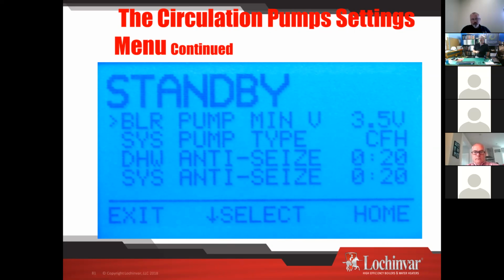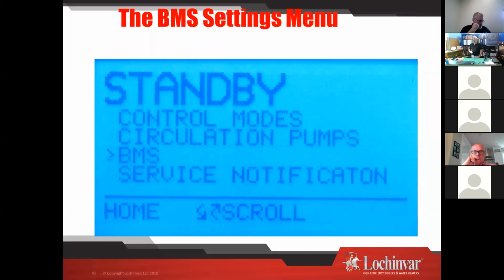Boiler pump minimum voltage is going to be set for 3.5 volts, and that's the minimum rate that it's going to run that pump. Now on the display screen, it shows you your boiler pump rate output, it doesn't show you the voltage, and on the screen that would show up as 35%. That's where it's dropped that pump down to.